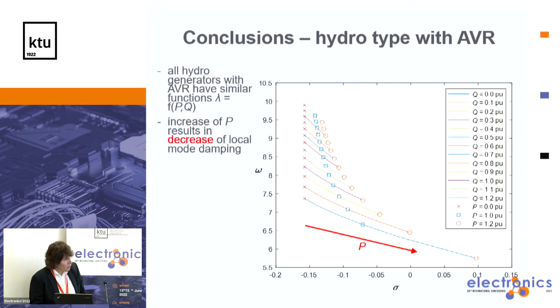Another conclusion is that Q again increases the frequency of local mode oscillations, and the stability high problematic area is when we have a high value of active power and low Q. This is especially dangerous, and the low problematic part, the best damped part of operation, is here with low P and low Q.